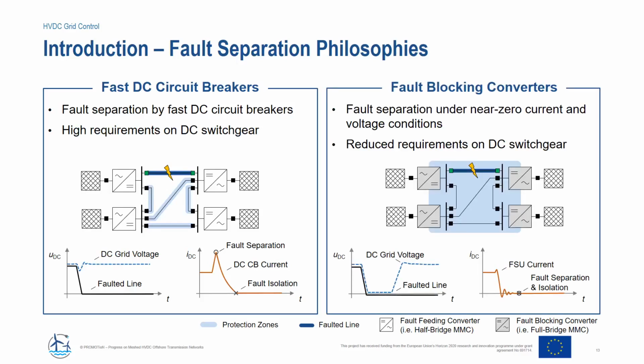An alternative approach is the protection of HVDC grids based on fault blocking converters. Here the entire grid is treated as one protection zone, and in the case of the fault, the DC voltage within the entire system collapses. All converters actively control their DC currents to zero, and thereby they stop to transfer energy from the AC into the DC system. After a short time, so several 10 milliseconds, this has been shown also in work package 4, the DC voltage, but also the current flowing through the DC switchgear, which shall separate the faulted line, decay to values very close to zero, and thus the requirements on the DC switchgear are much reduced compared to full-size DC circuit breakers.